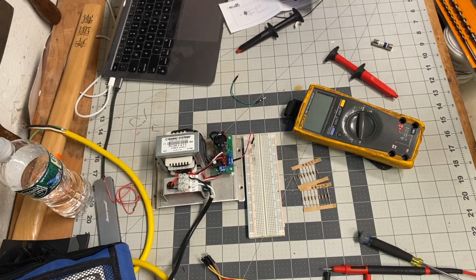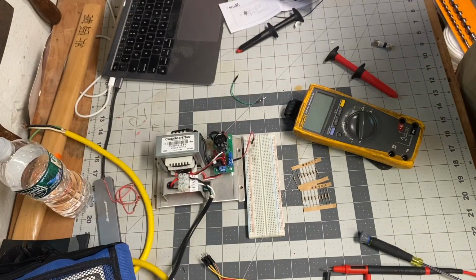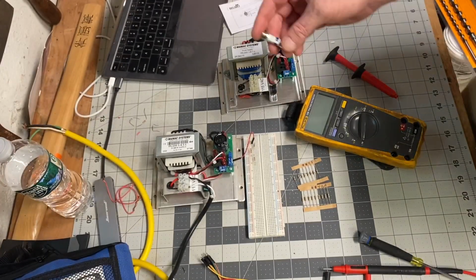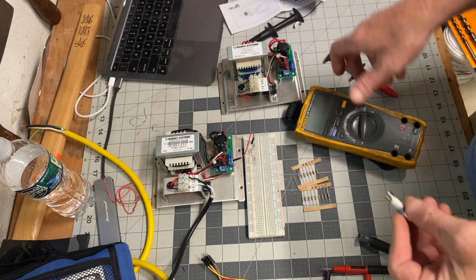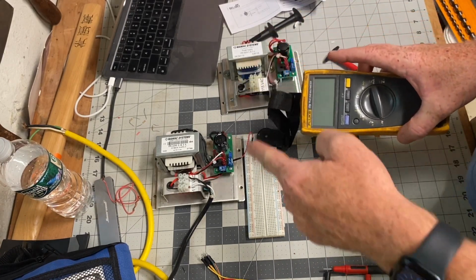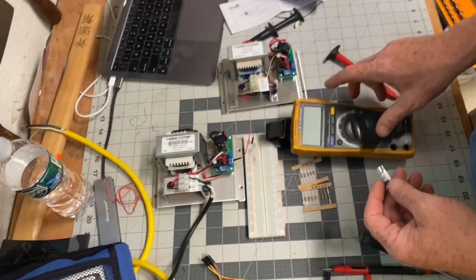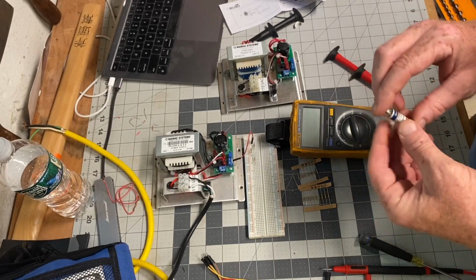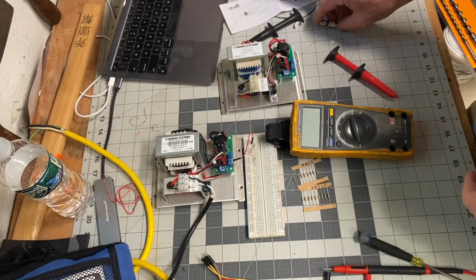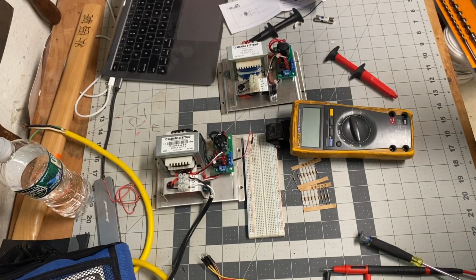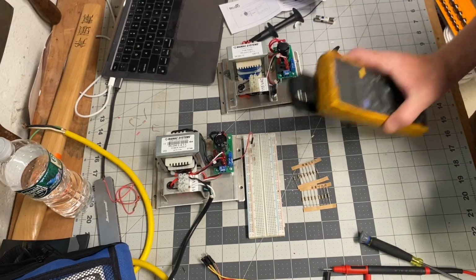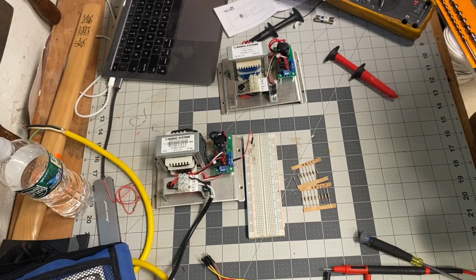All right, checking the operation of a Mamac power supply, take two, because I started recording this earlier, and when I went to check the milliamps across the circuit, I ended up trying to check the voltage and left the leads in the milliamp position, and kapow. So I done blew up my meter.